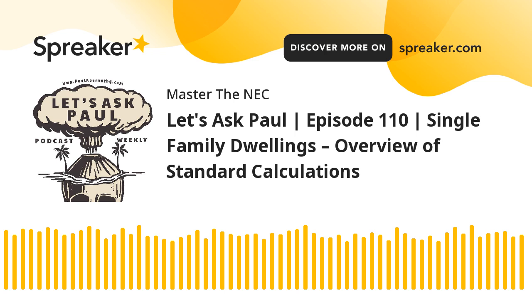It looks like at that point, we can get a 4-aught. And that is why you see SE cable 4-aught being the most commonly used for 200 amp service, because they figured that into it. It's all kind of taking care of itself. Okay. All right. Without getting too deep with that, let's kind of go back now.